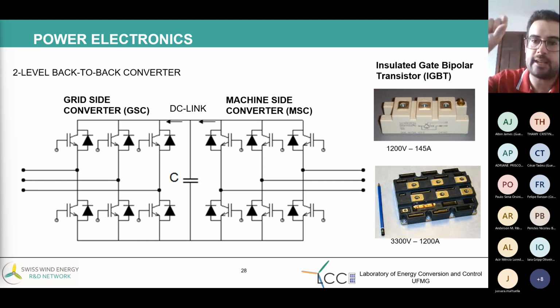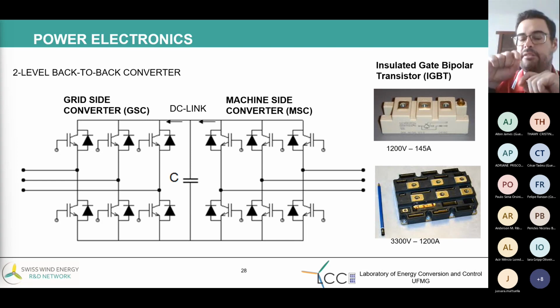If I put it in the nacelle, this means that we need space and a cooling system there. The space is a problem in the nacelle. If I put it at the bottom of the tower, I have a problem of cabling and connection. So it's not defined. Each manufacturer has its own way to place the power converter.